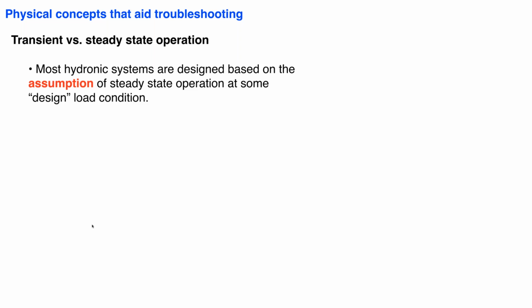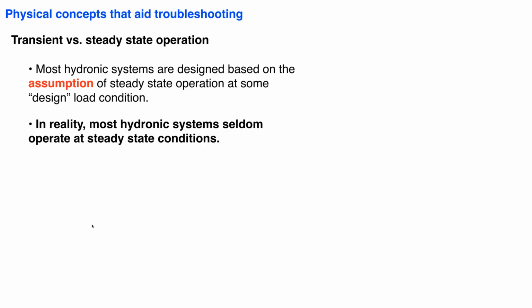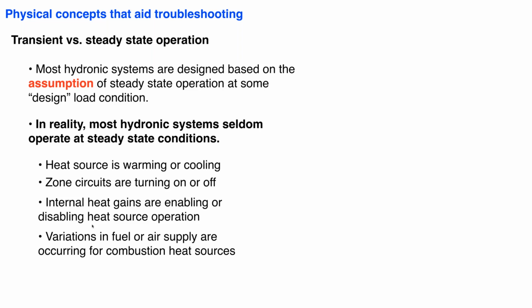So we're designing and selecting components based on this concept that the system would operate hour after hour after hour at some steady state design load condition. And the underlying assumption is that if it can do that, it can maintain comfort in the building regardless of how long that design load condition persists. But in reality, most hydronic systems are seldom operating at steady state conditions. What's happening? Heat source is warming up or cooling off. A thermostat calls for heat, the boiler's cool, it has to warm up. Obviously, the temperature is going to change as it warms up, or after the burner is shut off, it's going to cool down. We could turn zone circuits on or off. When we turn a zone circuit on, we'd have cool water coming back.